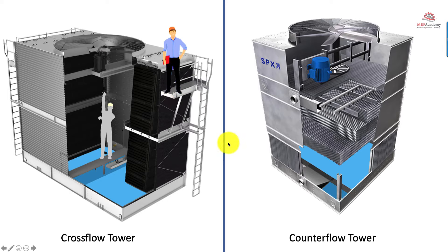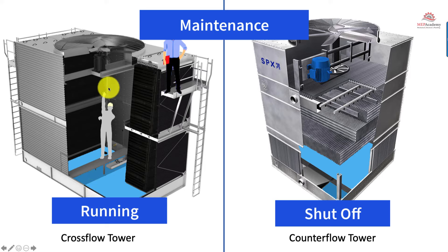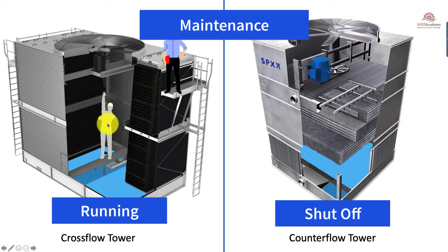Looking at maintenance differences: on the cross flow, you can maintain the system while it's running. The water trickles down to the side, so a maintenance person can come through an access door and use a walking platform above the cold water basin without getting wet. On the counter flow, you can't get inside while it's running because water trickles down over basically the whole footprint. Access to the motor must be from the outside or through an access door, as opposed to the cross flow where it's accessible from inside.